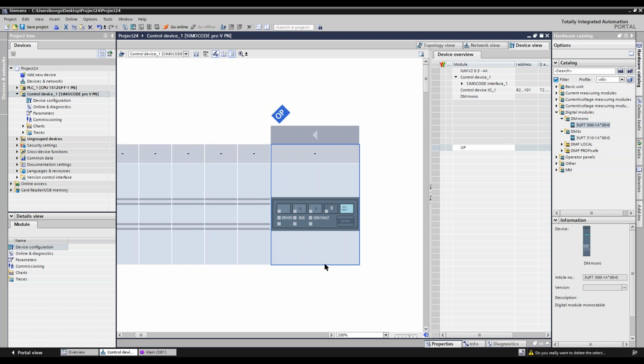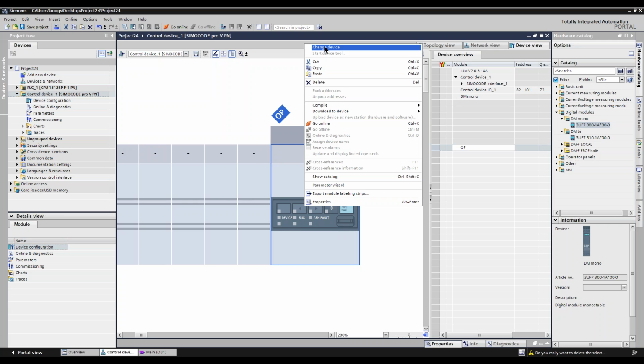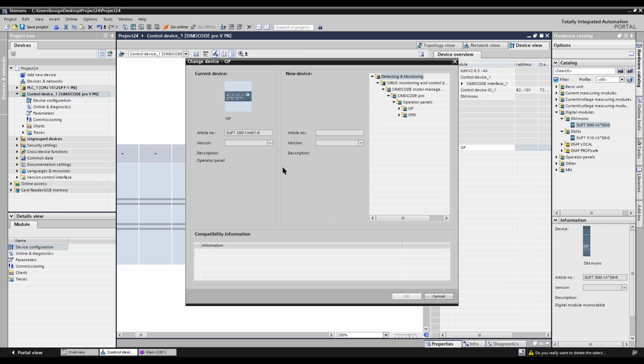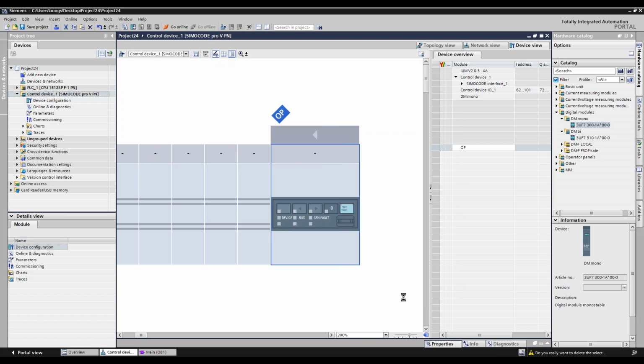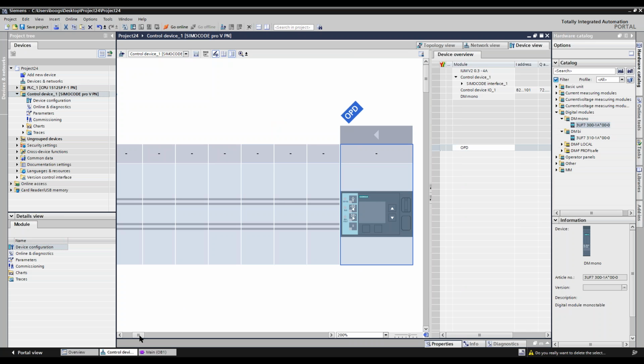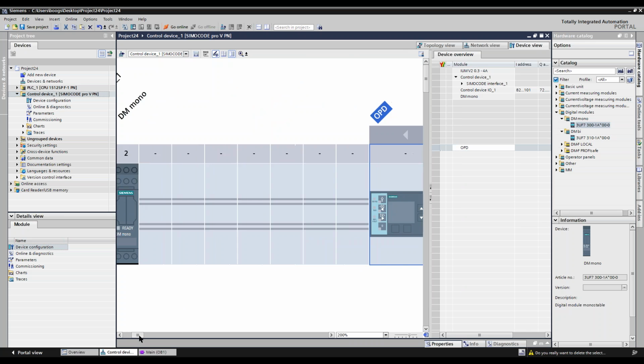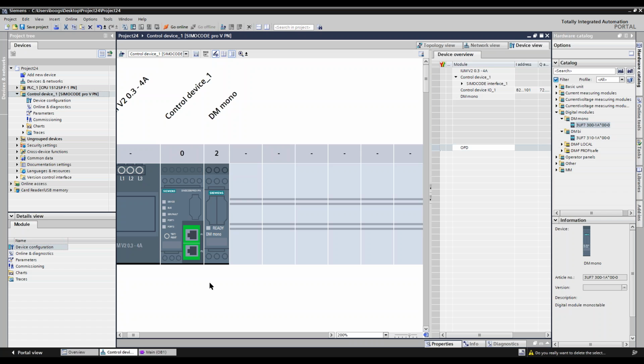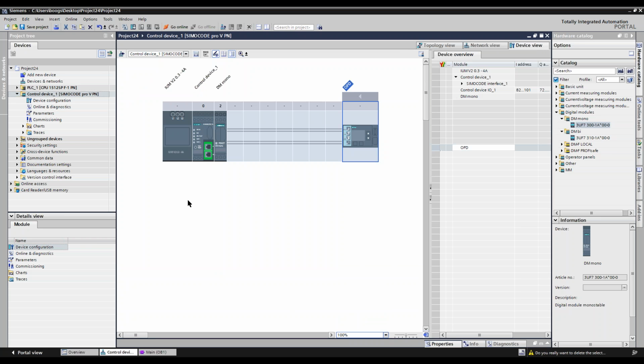Then also, I'm going to scroll over here. It defaults to putting in the non-display operator panel. I'm going to right click and say change device. I could just delete that if I didn't want an operator panel. And I'm going to go to, whoops, this one right there. Sorry. And hit OK. Changes that out. And now I have all my hardware done. I'm ready to download and start turning on my motor.